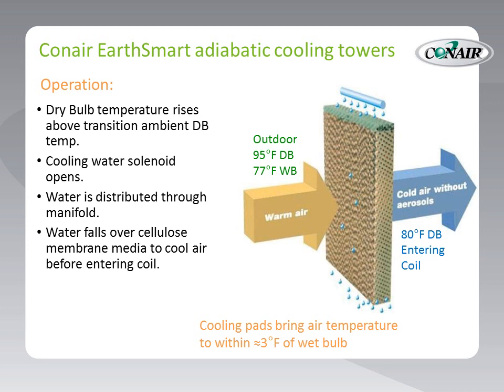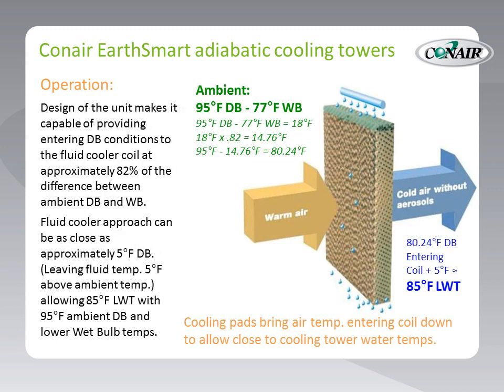In operation, as the ambient dry bulb temperature rises above the transition set point and the leaving water temperature set point can no longer be maintained by simply running the fans, the cooling water solenoid valve will open, allowing water to soak the pads and lower the dry bulb air temperature entering the coils. Units can be sized to deliver leaving fluid temperatures of 85°F with ambient conditions of 95°F dry bulb and 77°F wet bulb. EarthSmart adiabatic towers are capable of depressing the dry bulb temperature to 82% of the difference between the dry bulb and wet bulb temperatures. The approach temperature can be sized as close as about 5°F.